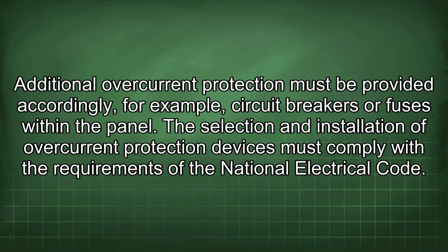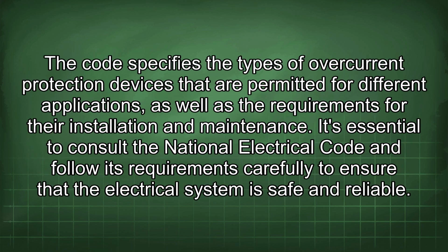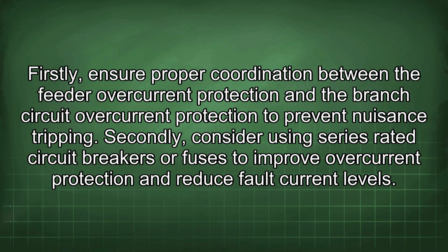The selection and installation of overcurrent protection devices must comply with the requirements of the National Electrical Code. The code specifies the types of overcurrent protection devices that are permitted for different applications, as well as the requirements for their installation and maintenance. It's essential to consult the National Electrical Code and follow its requirements carefully to ensure that the electrical system is safe and reliable. Firstly, ensure proper coordination between the feeder overcurrent protection and the branch circuit overcurrent protection to prevent nuisance tripping.